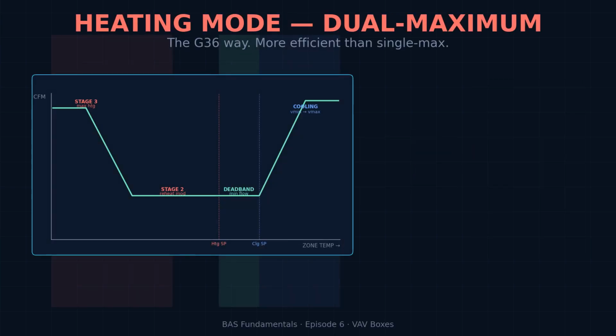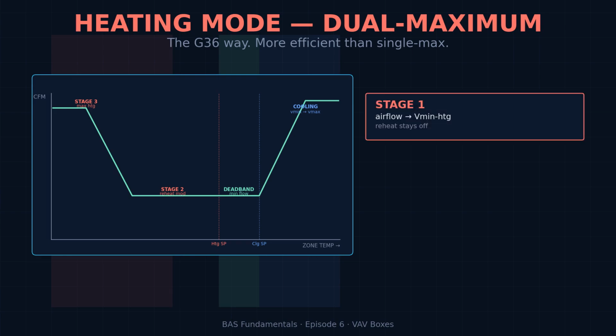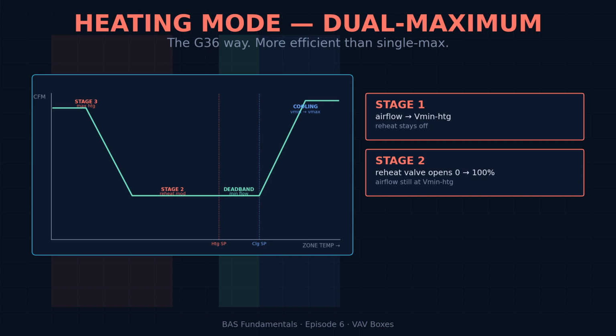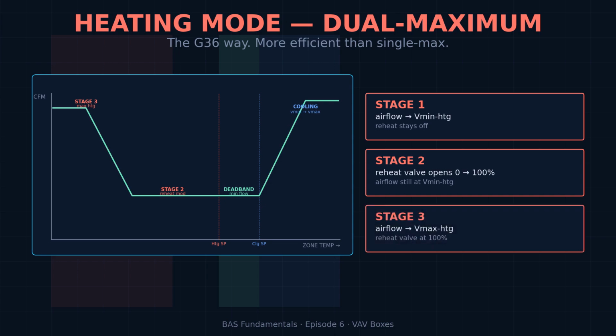Heating mode is where modern sequences get interesting. The old way was single maximum. On a call for heat, the damper just opened up and the reheat valve followed. Wasted energy because you were heating a lot of air. The G36 standard is dual maximum. Stage 1, airflow drops all the way to the minimum heating value, Vmin heating, which is usually just your ventilation code minimum. Stage 2, the reheat valve opens, 0 to 100%, to heat that minimum airflow. Only if you still can't meet the set point does Stage 3 kick in, where airflow ramps up to Vmax heating while the valve stays open.